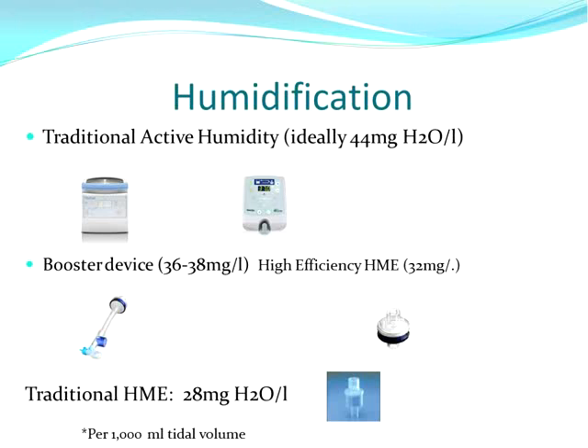Traditional HMEs will typically provide somewhere in the 28 milligrams of water vapor per liter, but we might be able to get some more high efficiency HMEs that will provide more. And then a new device that's on the market is the booster device, which utilizes both an HME, so passive humidification, and an active humidification system closer to the patient. These devices don't claim to be able to provide ideal humidity at 44 milligrams of water vapor per liter, but they get fairly close. So it may be an opportunity to start looking at how much the patient tolerates being away from that ideal saturation of water vapor.